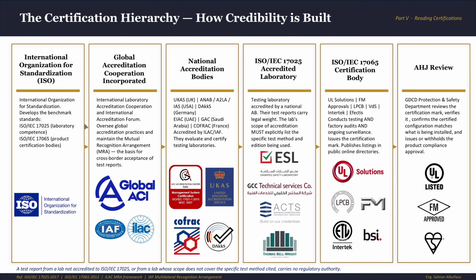The two standards that matter for us are ISO/IEC 17025 and 17065. ISO/IEC means that the standard was jointly developed and published by both organizations, the ISO and the IEC, the International Electrotechnical Commission. Going back to 17025, it's the international standard for testing and calibration laboratories. It enables labs to demonstrate that they can operate effectively and generate valid, globally accepted results. So any lab that does any kind of testing must have ISO/IEC 17025.